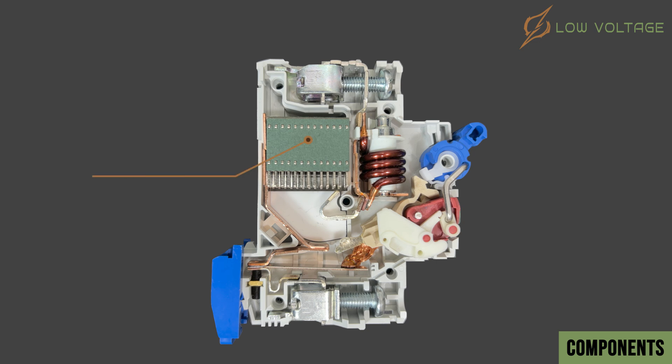When the MCB trips to disconnect the circuit, or in cases where the MCB is switched off on operating load, a high-temperature arc is generated between the moving and fixed contacts. This arc is controlled by the arc chamber, which consists of metal pieces arranged in parallel to split the arc into smaller segments, reducing its intensity and protecting the internal components of the MCB from damage.